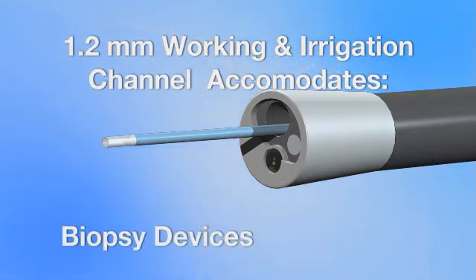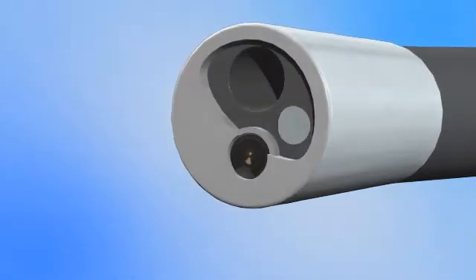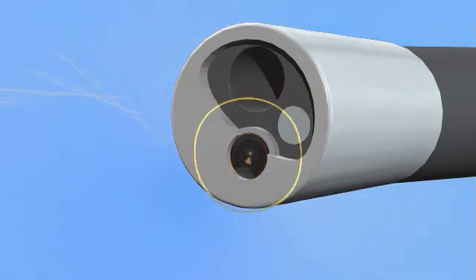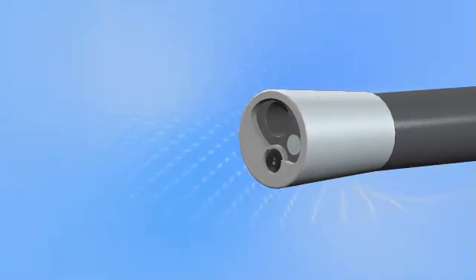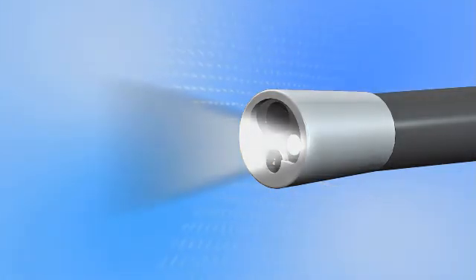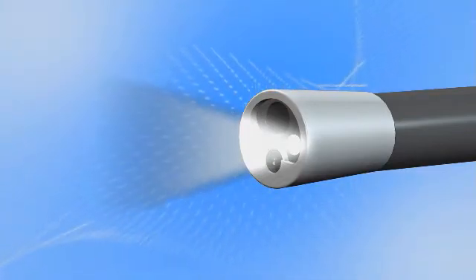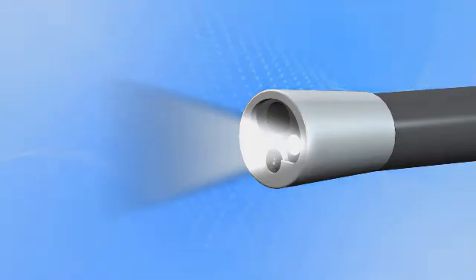balloons, and biopsy devices. The fiber optic channel is sealed by a diamond glass plate, which closes the optic channel hermetically. Because of this, the fiber optic never comes into contact with the patient and does not need to be sterilized between cases. The lighting fiber is incorporated into the disposable catheter system and is not part of the fiber optic.